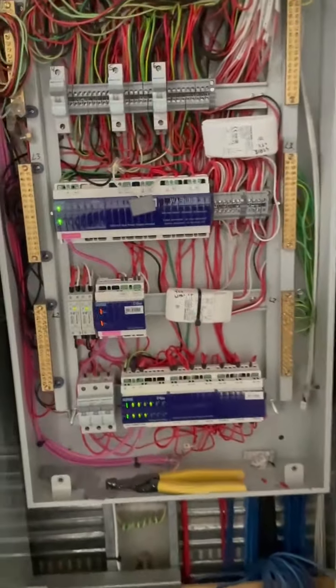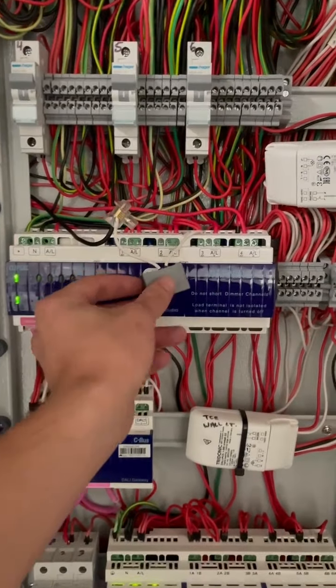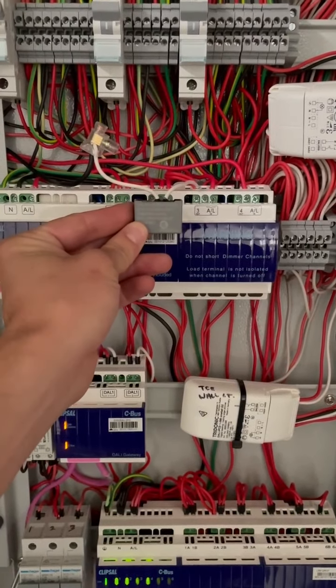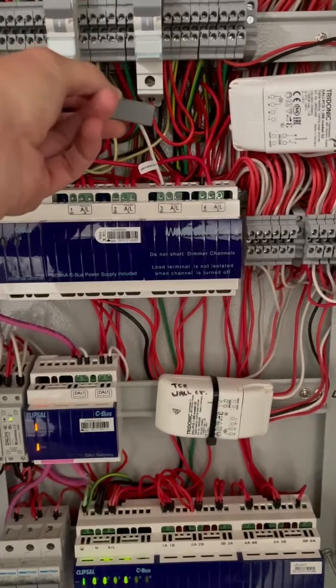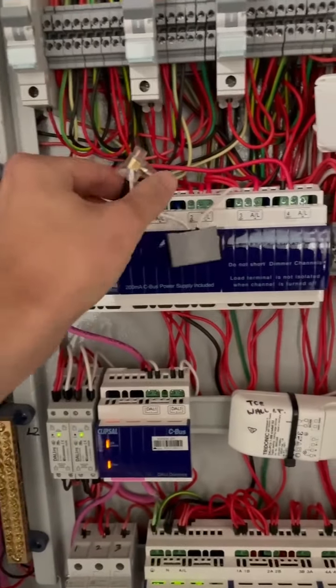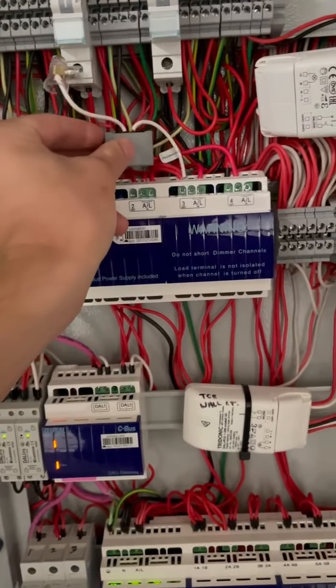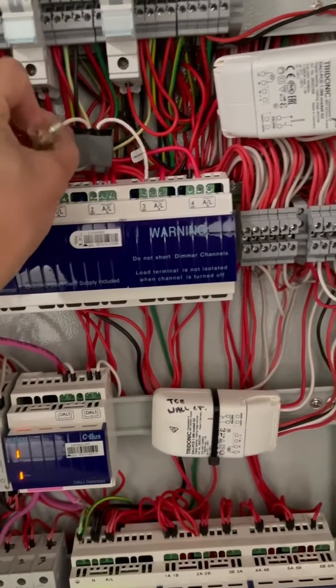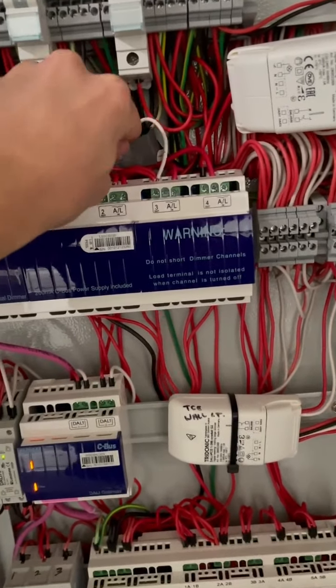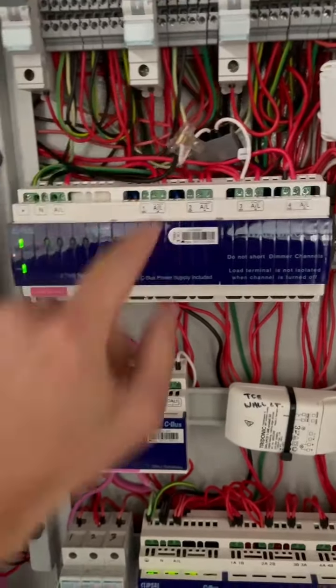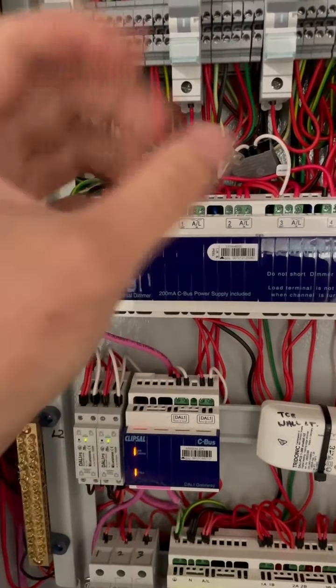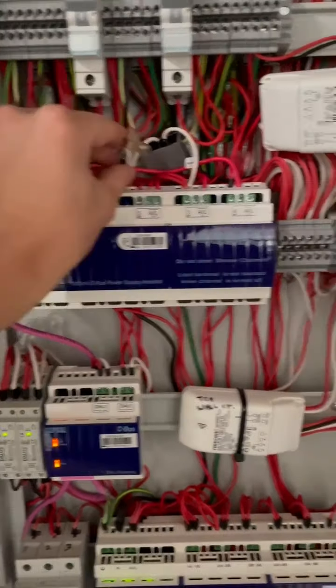Okay, here's a little tip. This is a lighting control electrician's best friend. It's called a load correction capacitor. Basically, put it across the switch wires in a neutral and it adds load to the circuit, so it stops flickering of LEDs. Sometimes in phase dimming in C-Bus and other systems, when it's turned off, the lights will still flash because there's a little bit of load. So that eliminates all of that.